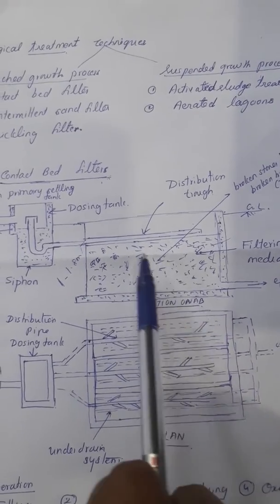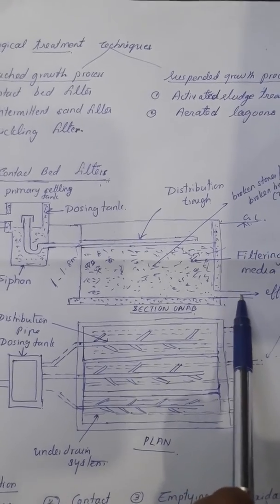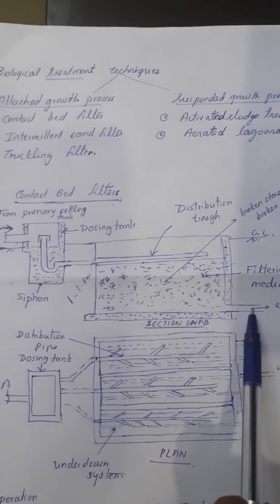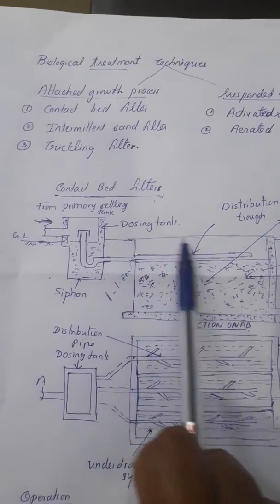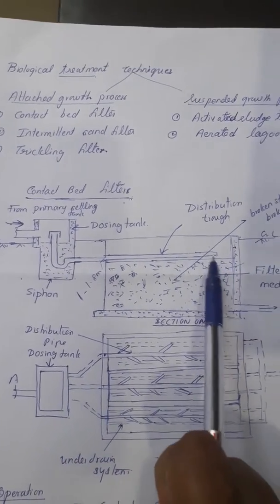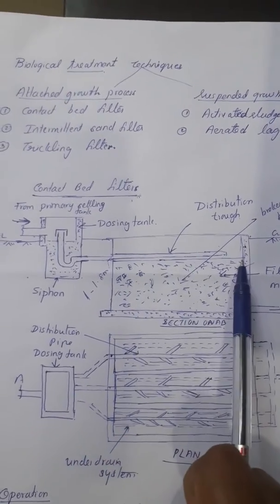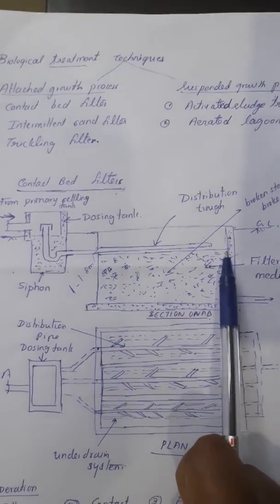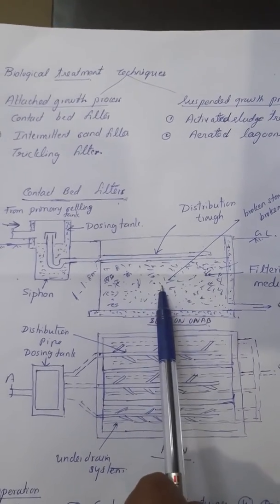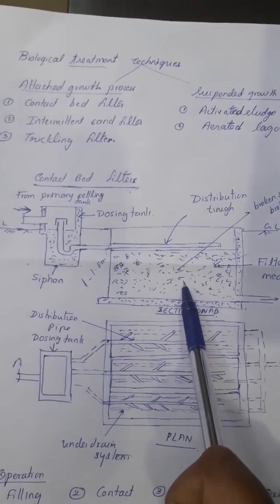From the under drain system, the effluent can be sent to the secondary sedimentation tank for settling out the oxidized organic matter. The sewage is uniformly applied over the entire surface of the contact bed using the distribution trough. The sewage is uniformly spread onto this contact bed, and the rate of loading is very low, varying from 4000 to 6000 cubic meters per hectare per day.